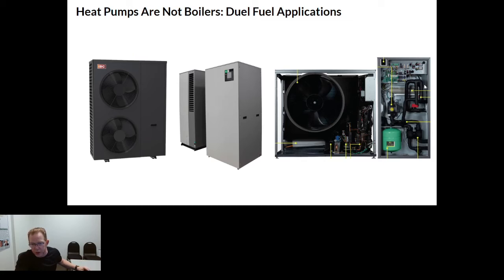So the unit on the right-hand side, I've actually got an open shot of it so you can see inside of it. When you look inside of this unit, you can see it's got a variable speed pump built into it. It's got an expansion tank built into it. These are actually flushing ports, so you can flush it right inside of the unit. The System M is similar on the inside of it. Right here, you can see that the 9 kilowatts of backup heat is built right into it.